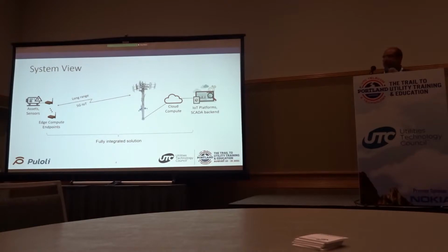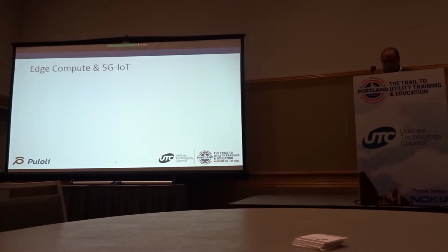Whereas in the case that we are talking about, edge compute is extended across the link on the other side to the endpoints. That's the definition of edge for the purpose of edge compute in this context for utility use cases. It is very important to internalize this, because that's not the most common definition in the industry today. For us, edge is all the way across the radio link, because for utility and critical infrastructure use cases, we see the need to have that on the edge for many different reasons, including supporting existing soft PLC functions, controls and measurement functions that are needed to realistically deploy some of the use cases.